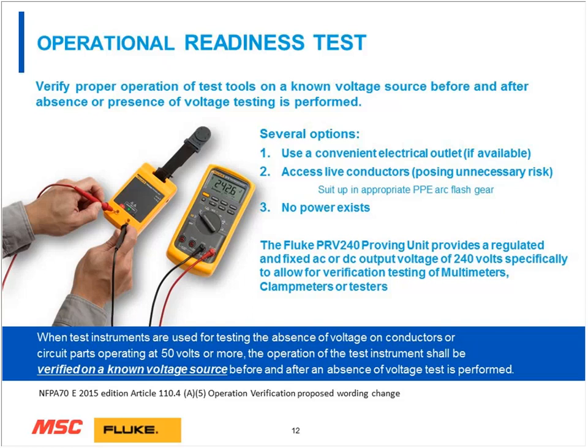In the operational readiness test, we use what's called a proving unit, and that generates a certain amount of voltage that's suitable for the environment. It's a known voltage. You could use a convenient outlet, but if you use lockout-tagout, chances are that outlet is no longer powered. So this is called the PRV240. It's a small proving unit that generates 240 volts, AC or DC. So if you're working on a backup power supply on batteries, you can use the DC section. You verify the operation of the instrument, then you measure the unknown, and then you re-verify.